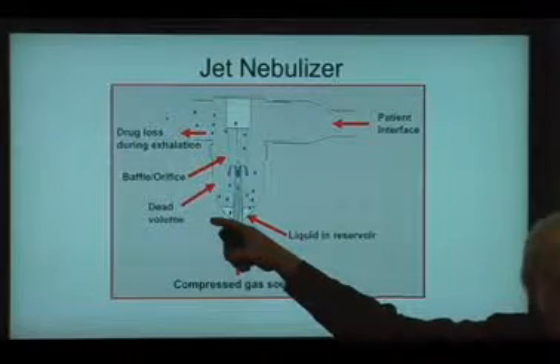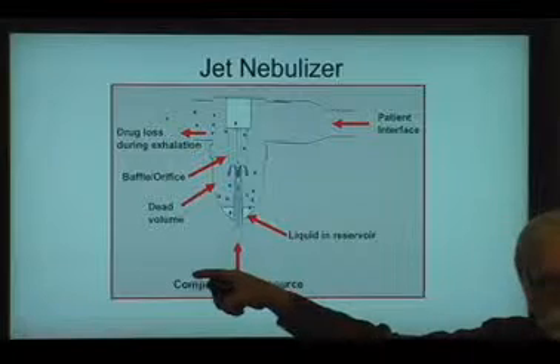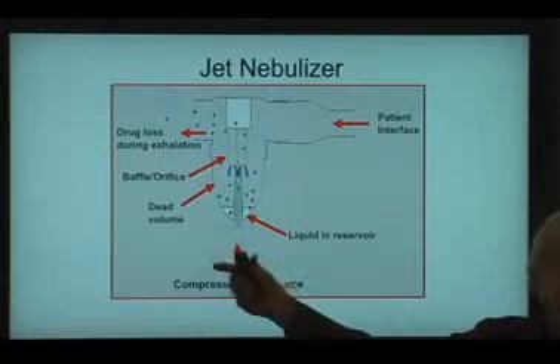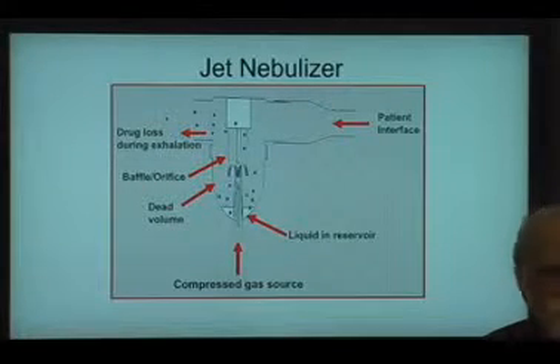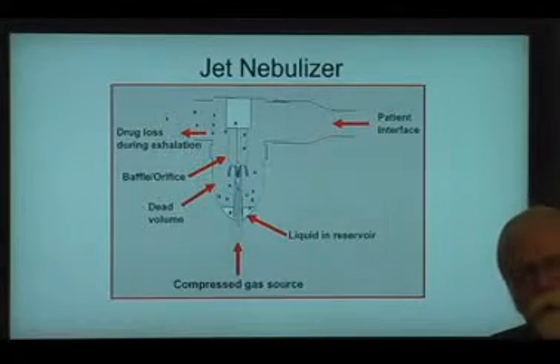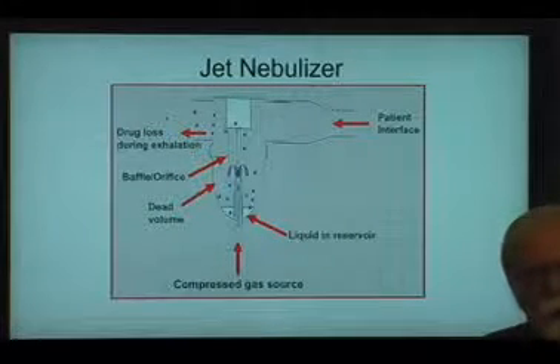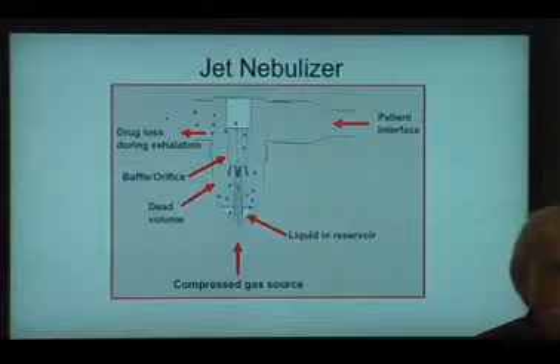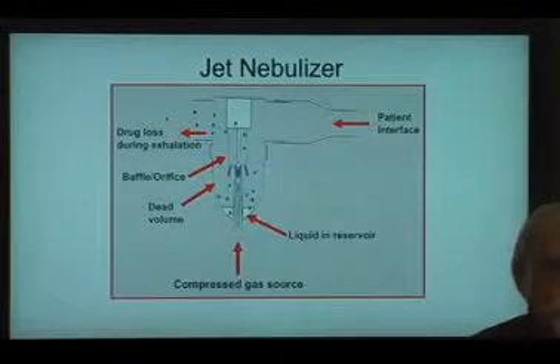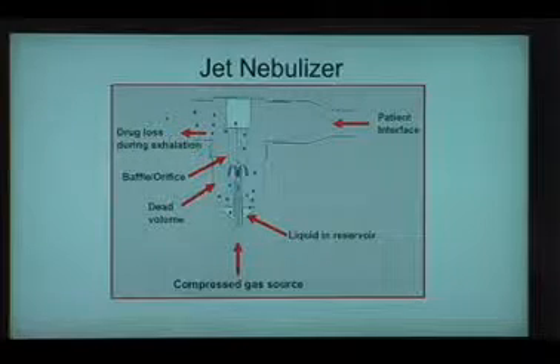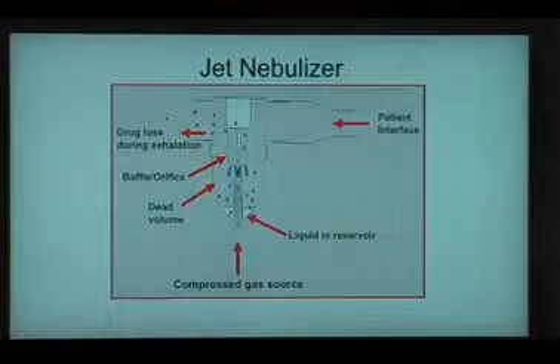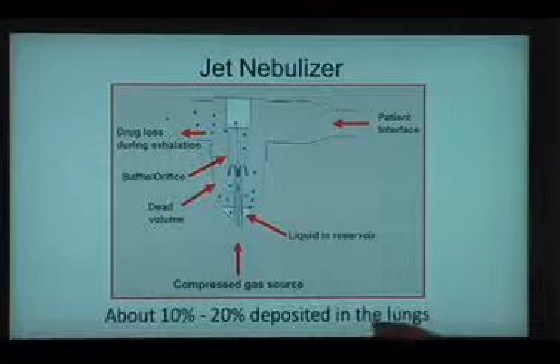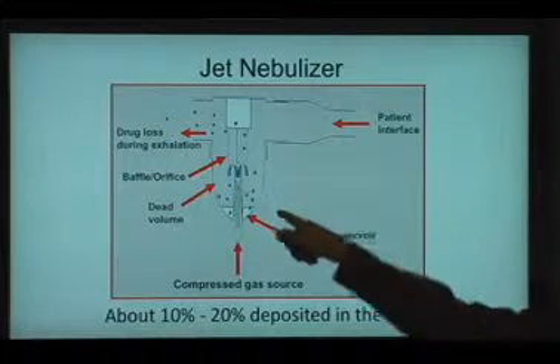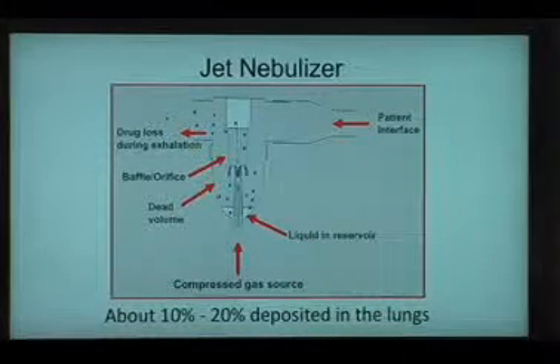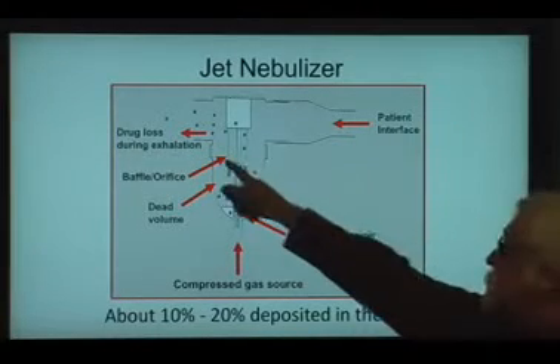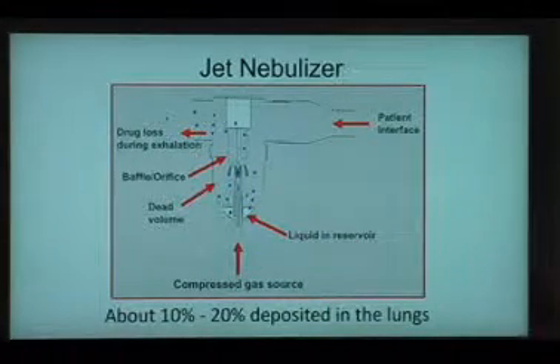So you can imagine if you only put 2 milliliters of solution into the nebulizer, half of it never gets aerosolized because it's the dead volume of the nebulizer. So think about that when you think about putting 2.5 milliliters from a unit dose vial of albuterol into the nebulizer. Half of that gets shaken out at the end of the treatment or gets thrown away with the nebulizer and never gets aerosolized. New devices such as the mesh nebulizer get around that. So bottom line is that only about 10 to 20% of what we put into the jet nebulizer actually ends up being deposited into the lungs, because a lot of it gets wasted during exhalation, is trapped in the nebulizer dead volume.